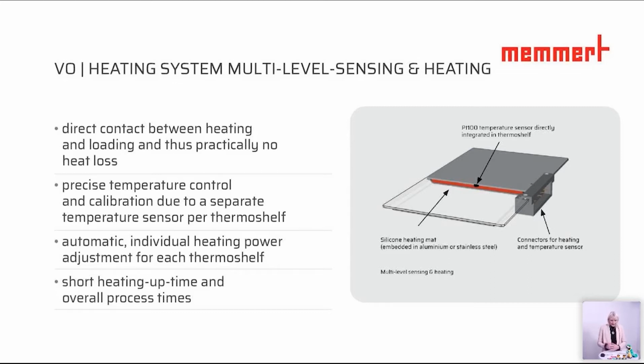This gives a short heating-up time and shorter overall process times, which is included because we have direct heating on the shelf. Furthermore, each shelf can be calibrated individually and separately using our Atmo Control software, which is included in the delivery when you get a vacuum oven.